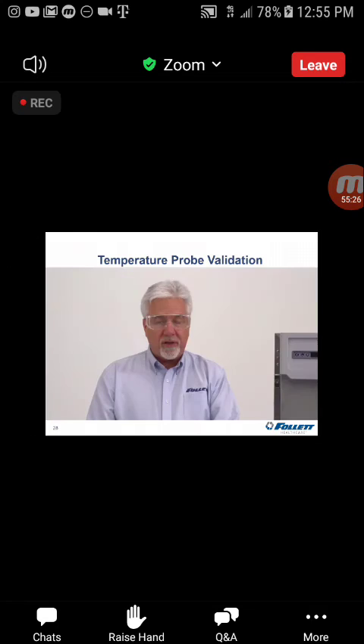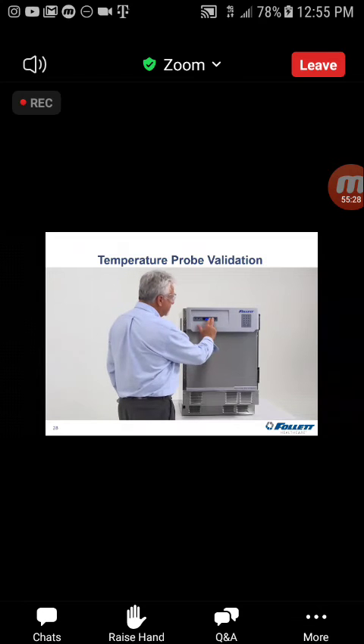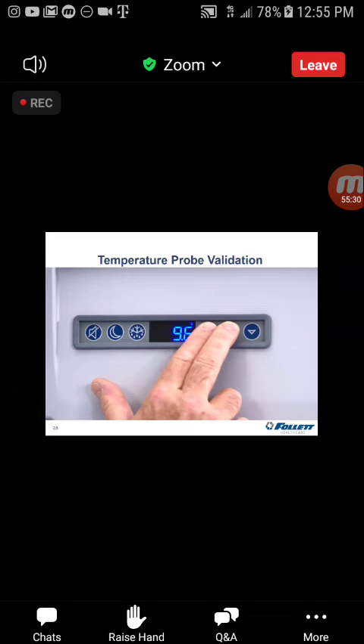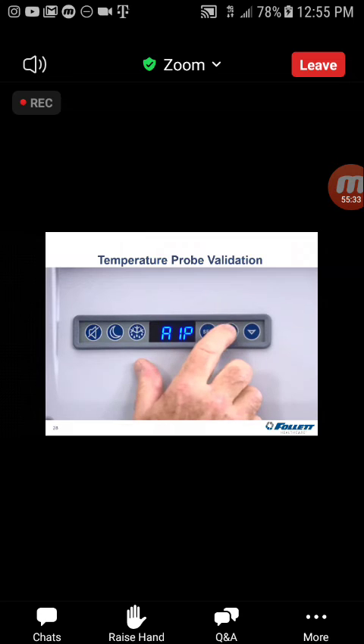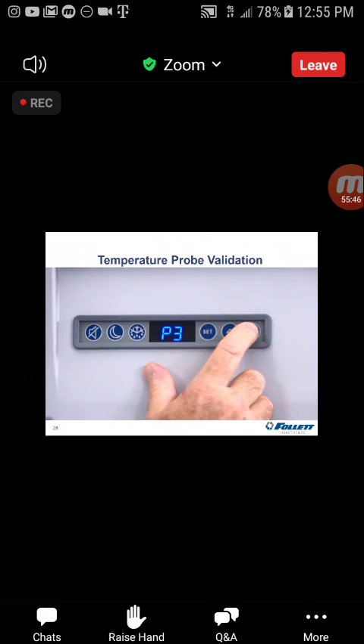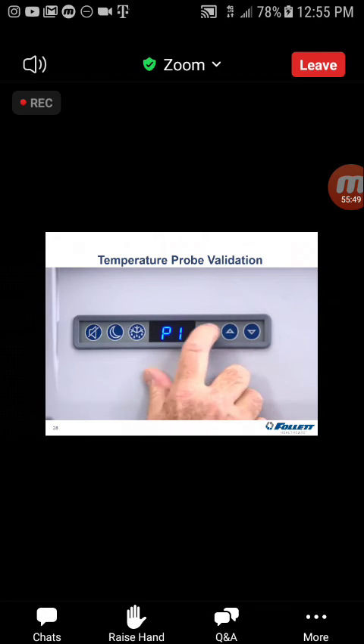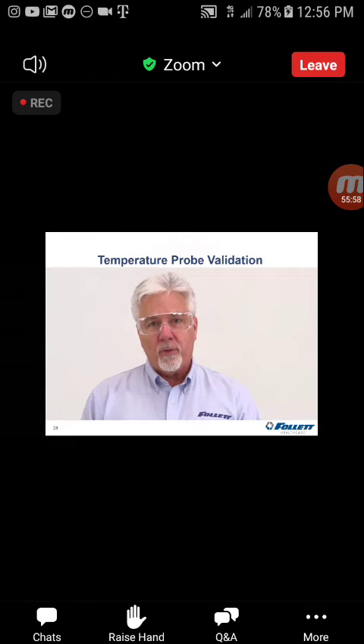Then we need to change the display setting. We go to the first level of hidden menu by pressing the set button and the arrow closest to it until L1 is in the display. Then use the arrows to scroll until you see DPR, which stands for display probe. Press set and you will see P3 in the display, which is the factory setting. Then use the arrows to change the setting to P1 and press set to accept the change. The temperature display will now display the temperature of the P1 control probe.